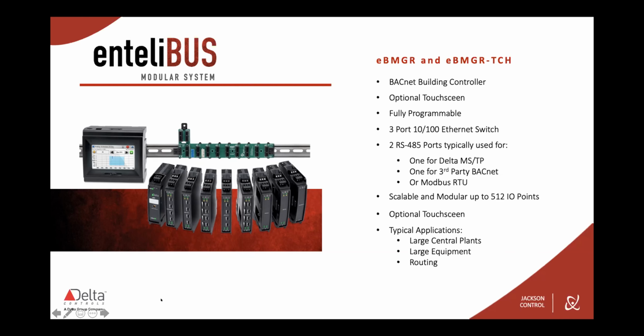The enteliBUS platform is a modular offering, so it can scale up to 512 I/O points—as small or as big as you want. It's fully programmable, with a built-in 3-port switch so the main network and building network can come into this. If there are other Ethernet devices in the mechanical room, you can use this as a switch to reach them, and usually people keep a third port open as a service port to plug in a laptop.